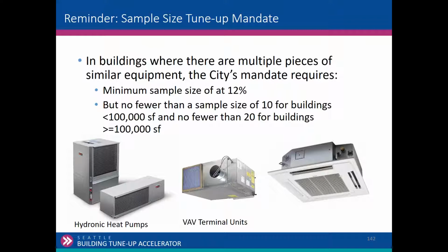But you need to correct those deficiencies and probably recommend to the building owner, I recommend that we go ahead and test the remaining VAV boxes and see if this is similar. Do another 10, or we keep seeing a pattern. But all you have to do is the minimum sample and correct those deficiencies in the minimum sample size.